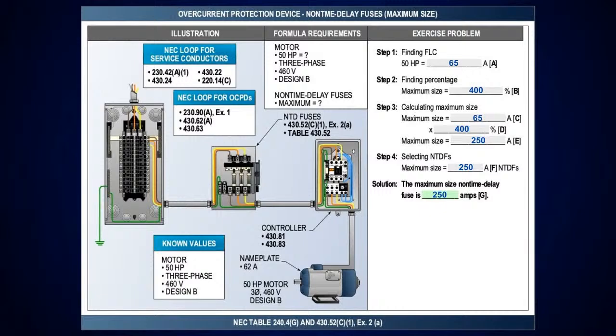Okay. Now, this one, this is your maximum size. All I'm going to be doing is looking right at 430.52(C)(1) and come down, depending on what cycle you're in. You'd be exception 1 and exception 2, or if you're in 2023, it'd be C1A and B. So it's the same calculation, same percentages. They just changed it so that instead of exception, it's full code text now. But look at this. I've got the same motor here. Now I'm going to look at the maximum. And if I drop down to exception 2, or I'll look at C1B, depending on which one y'all are looking at, you come down, you pick it up.